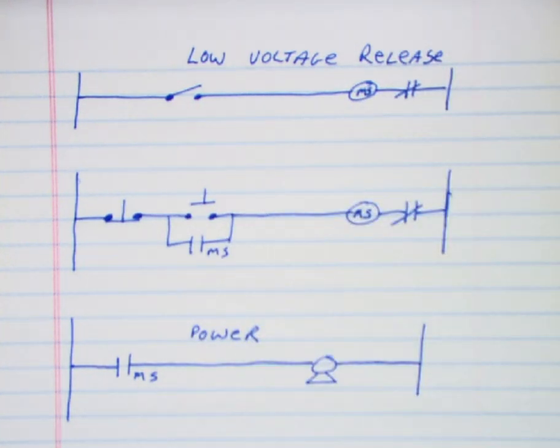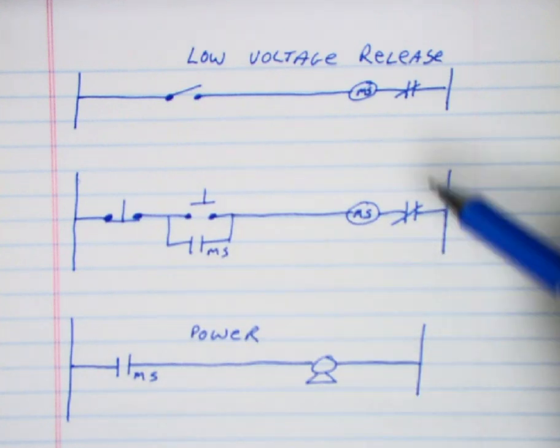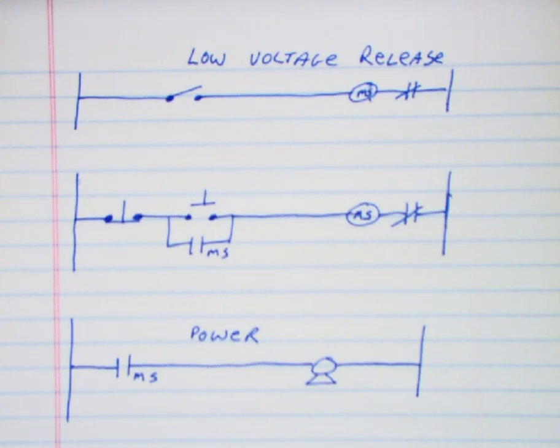Every time the voltage in the control circuit becomes low enough that it can't hold the contactor in, it releases. Every time the power comes back on, provided the switch is closed of course, when the power across that circuit comes back that contactor will pull back in and that motor will restart.